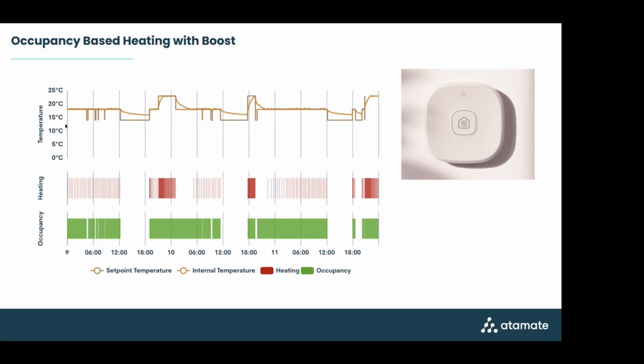So we've got three set points. The first is when it's unoccupied, that's this bottom line. The second is when someone goes into that space, then you go to the occupied line. And the third is a boost temperature, so if someone's cold they can go in and boost the temperature, which allows people to feel comfortable. One of our key objectives here is to get rid of portable electric heaters, because if you don't give people the ability to boost, they end up taking control themselves, buying portable electric heaters, leaving them on, and they're much less efficient. We'll come on to that in a while.